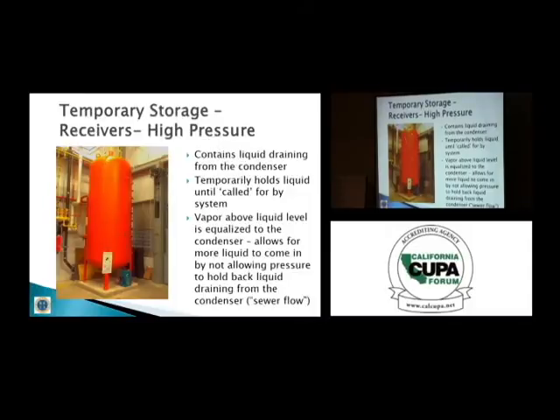Again, going down through the cycle, here's an example of one of those wide spots in the pipe where the refrigerant will fall into this, and the level can change throughout the day. Again, the reason the level changes is because of what's going on out there at the evaporator side. If nothing ever changed with the evaporator, if the need rate was always constant, you wouldn't need very much of a vessel. But in refrigeration systems, well, even in your refrigerator at the house, the tubing that comes down from that little radiator grid that's on the back of the refrigerator to its pinch point, that's a wide spot where the refrigerant can languish until it needs to be pushed into and through the evaporator.